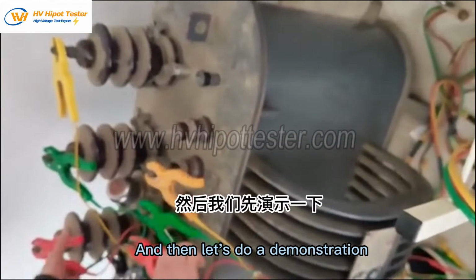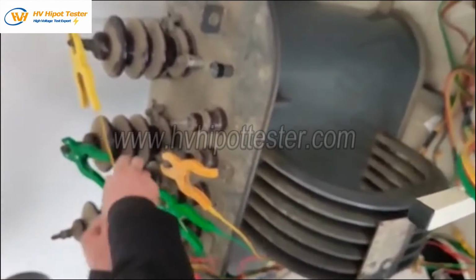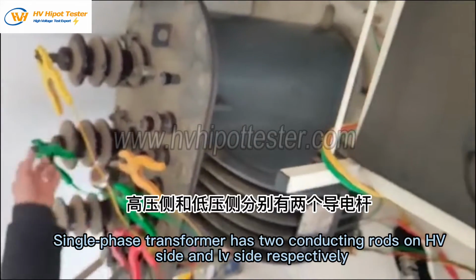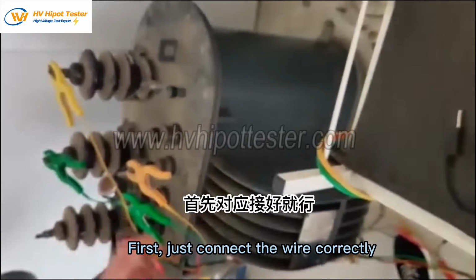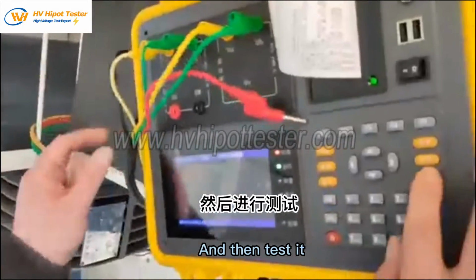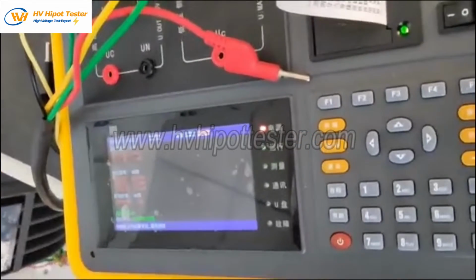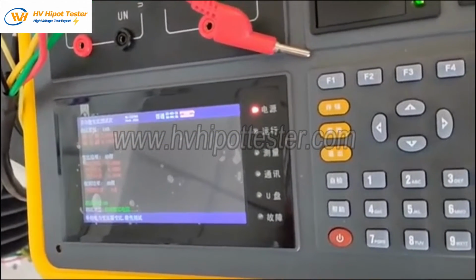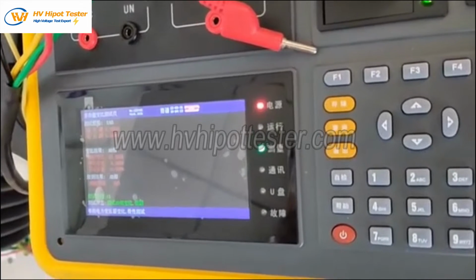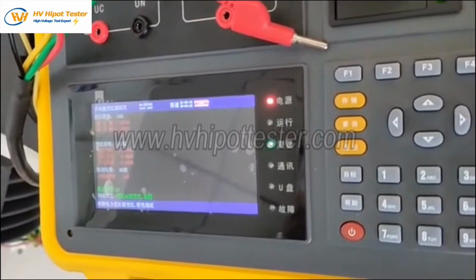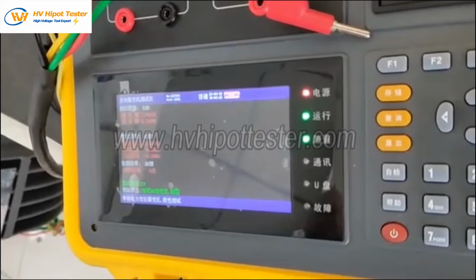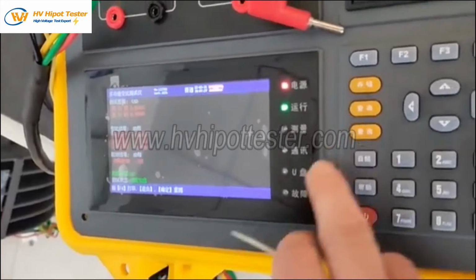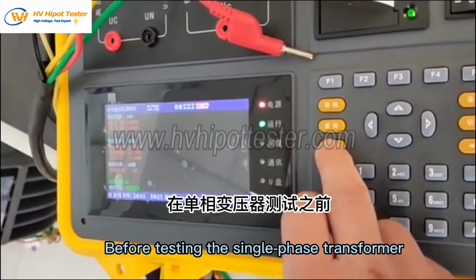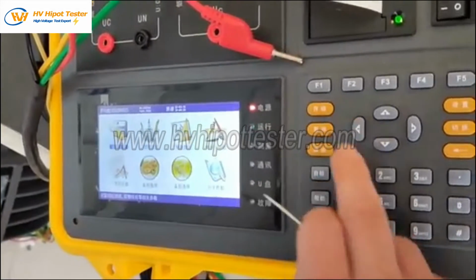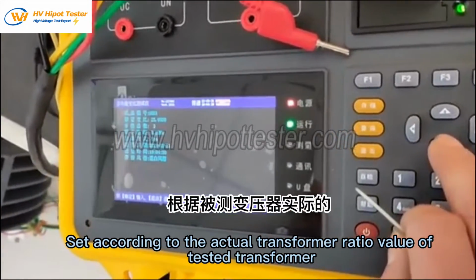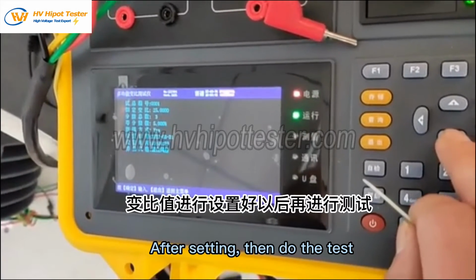And then let's do a demonstration, because this is a 3-phase transformer. Single-phase transformer has 2 conducting rods on HV side and LV side respectively. First, just connect the wire correctly, and then test it. Before testing the single-phase transformer, enter the parameter setting as well, set according to the actual transformer ratio value of the tested transformer. After setting, then do the test.